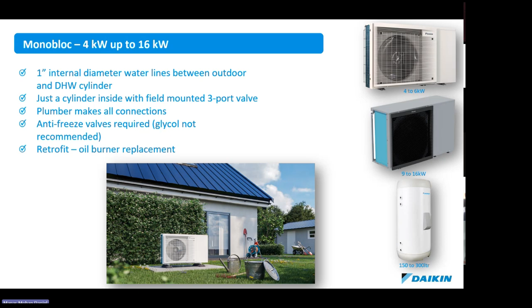You're restricted to about a 10 meter to 12 meter run. Because, as I say, you have heat losses immediately because the unit is producing hot water outside, sending it inside. So the pipework must be very well insulated at that. Plumber makes all the connections, antifreeze valves will be required. And it's a great retrofit, straightforward for an old oil boiler that's there as well, providing all the fabric upgrades are done inside and radiators in particular are sized right.